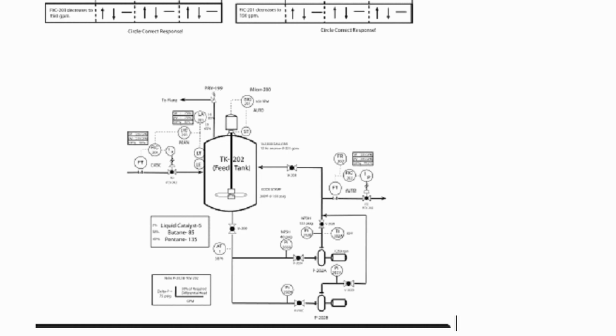But before that, the flow transmitter, once the liquid has been received, will send an electrical signal to the FIC, which is actually the flow indicator controller. Then off to the IP, which is a transducer. Then it would travel up towards the LIC, which is a level indicator controller. Then it would travel first to an LA, which is a level alarm.